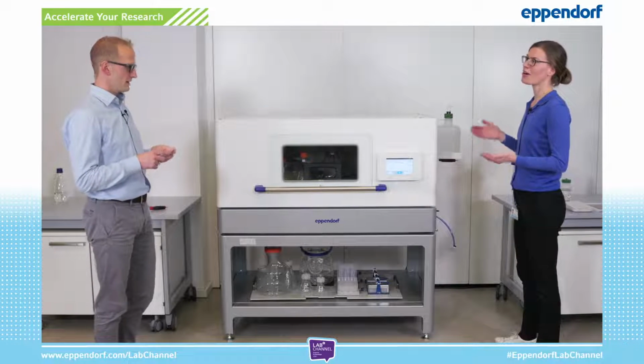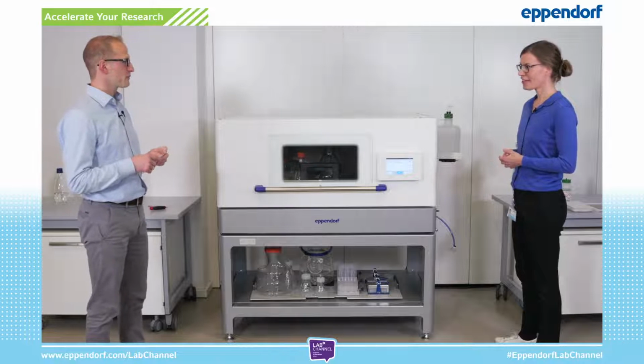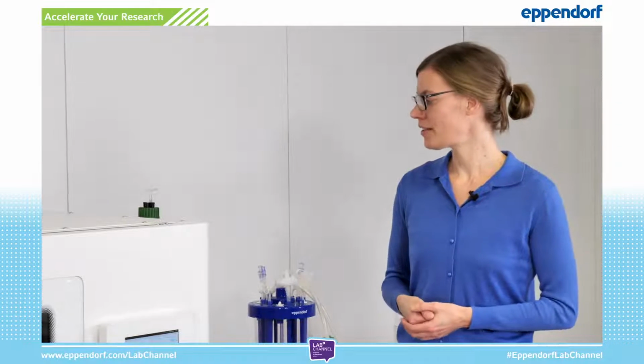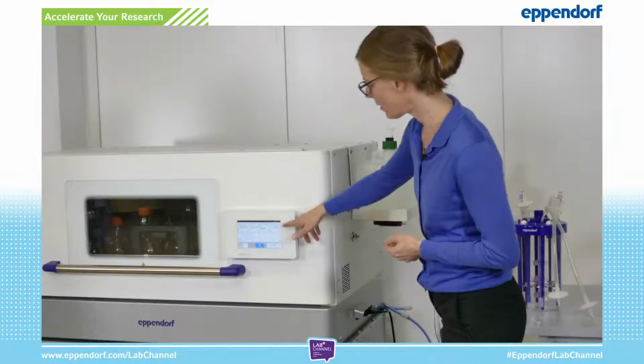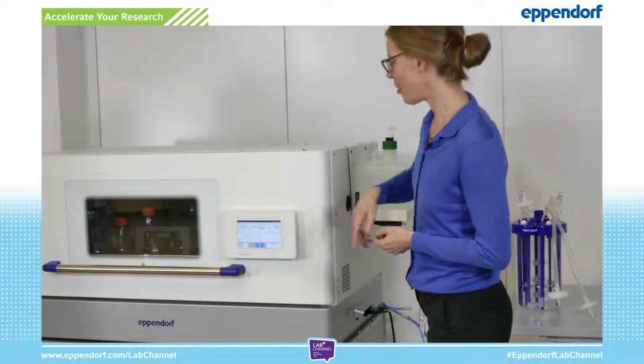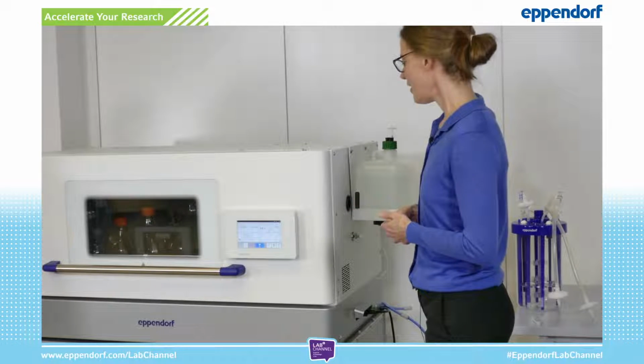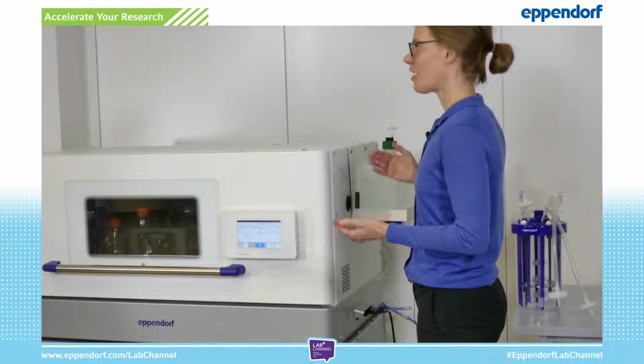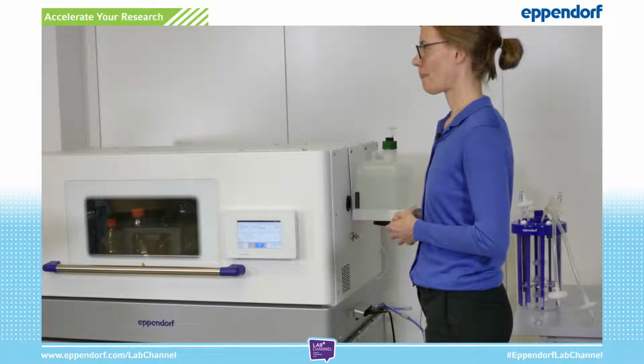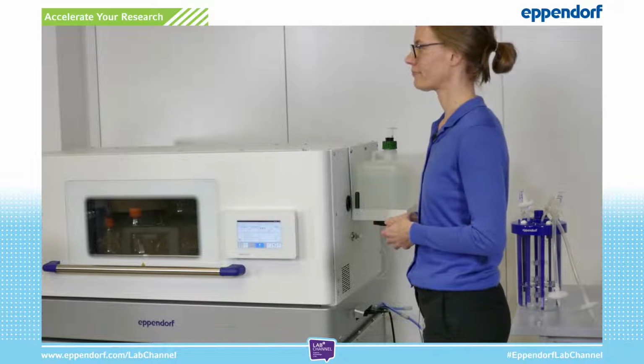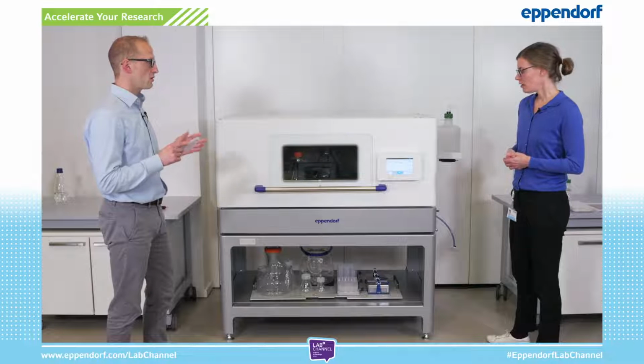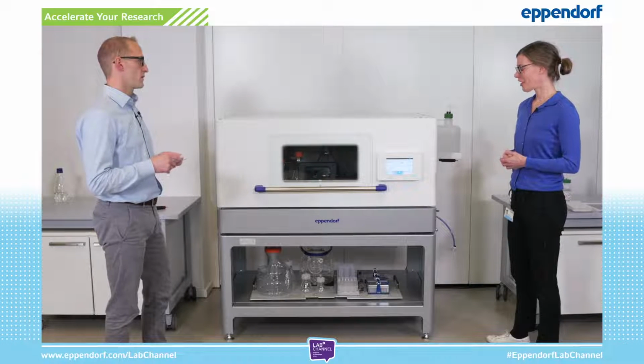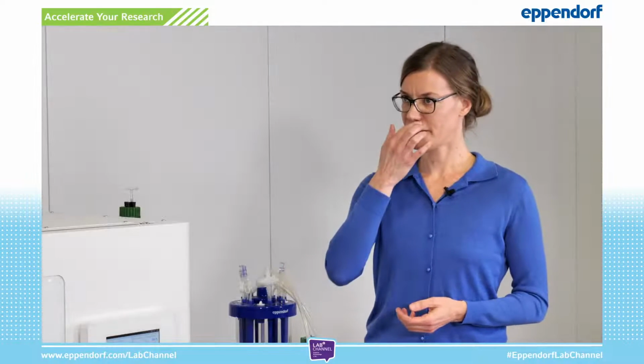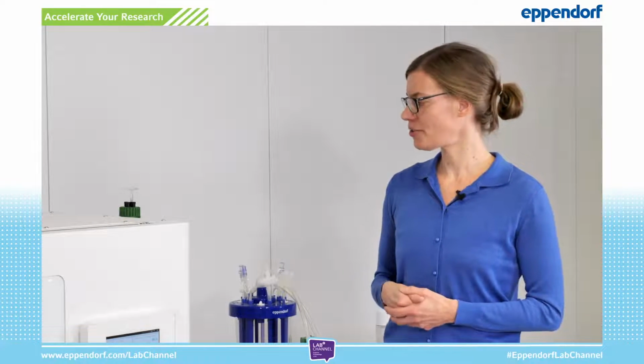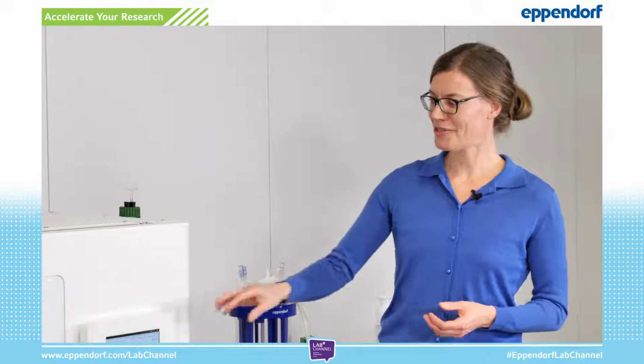Exactly. That is the new thing compared to our S41i. This comes with active humidification. So the S41i has water trays, so it evaporates. Also good, but active humidification has real control. You have a sensor inside and you can set it here on the display. You also have the value on the display. Mostly it's 80% that is set, and you have active control. So it's limited to 85%, you said? 85%. Okay. And I guess one of the advantages is a lower contamination risk than before? Exactly. In our feedback from customers, we heard water trays are a little bit more prone to contamination. You have to change them, but also the active control is really a safety to be at 85%.